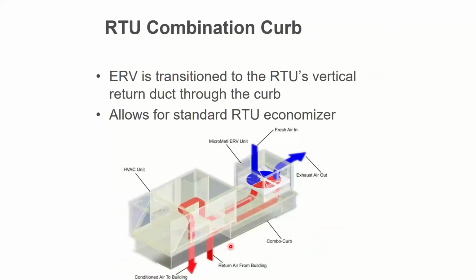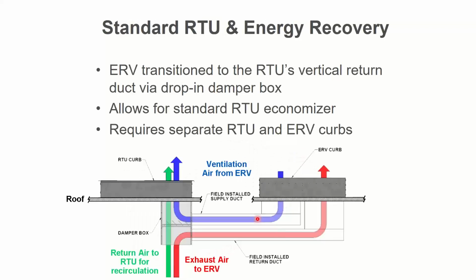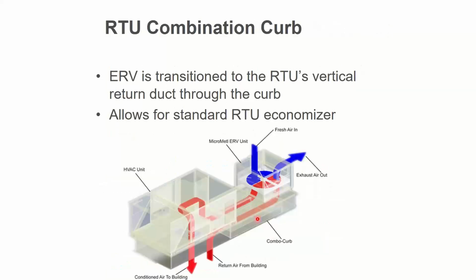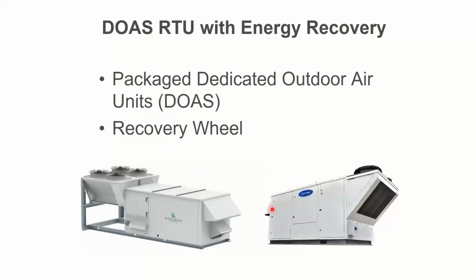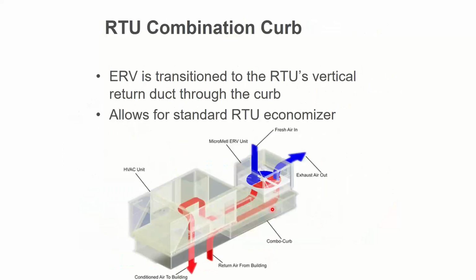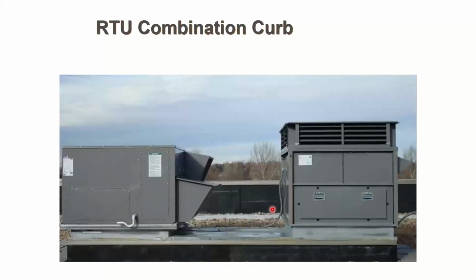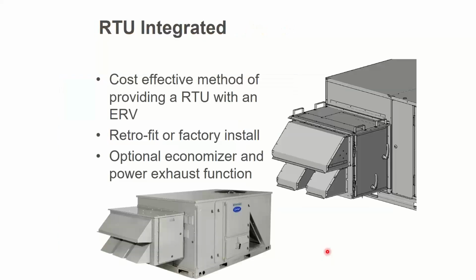You could get a curb that we call a combo curb that has this ducting physically inside the curb instead of you building it in the building. And I can have the air exchange happen that way between a standard rooftop and an ERV. The reason we do that sometimes is because standard rooftops are pretty inexpensive. Not that we can't do it this way. You certainly can, and some applications need that. But on other jobs where I only have, say, 50% outside air, this may be the way to go. It's kind of ugly. I got a rooftop and an ERV sitting on one giant ugly curb. But, hey, no one's looking at the curb on the roof, so who cares?